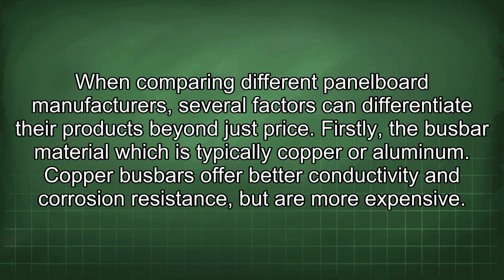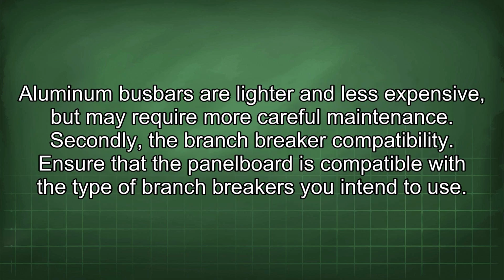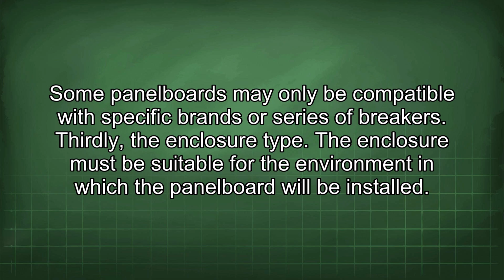When comparing different panel board manufacturers, several factors can differentiate their products beyond just price. Firstly, the busbar material, which is typically copper or aluminum. Copper busbars offer better conductivity and corrosion resistance, but are more expensive. Aluminum busbars are lighter and less expensive, but may require more careful maintenance. Secondly, the branch breaker compatibility. Ensure that the panel board is compatible with the type of branch breakers you intend to use. Some panel boards may only be compatible with specific brands or series of breakers.